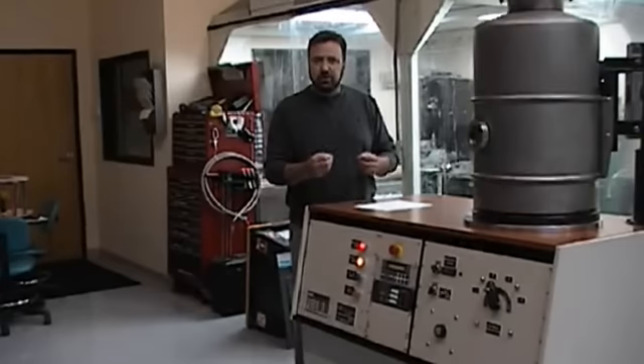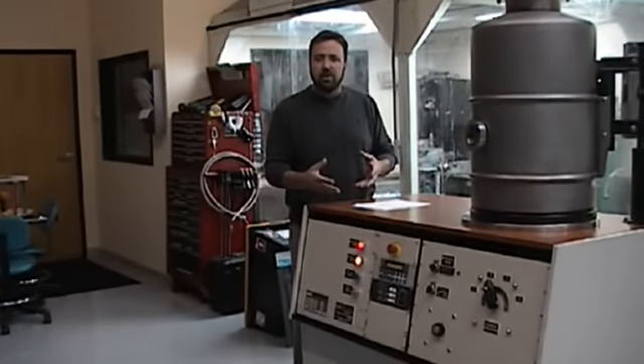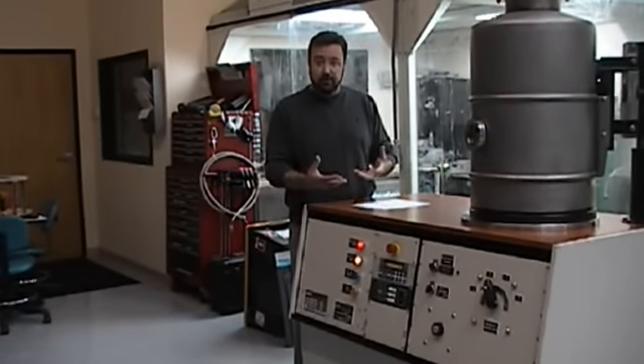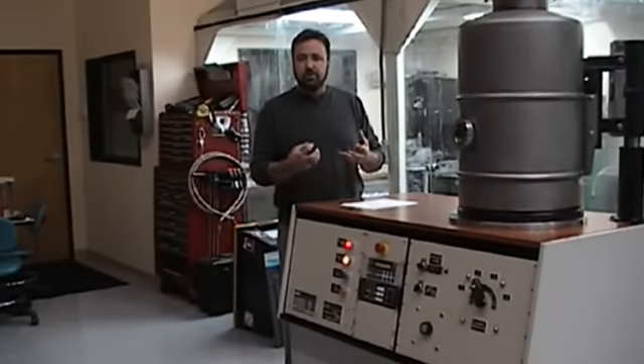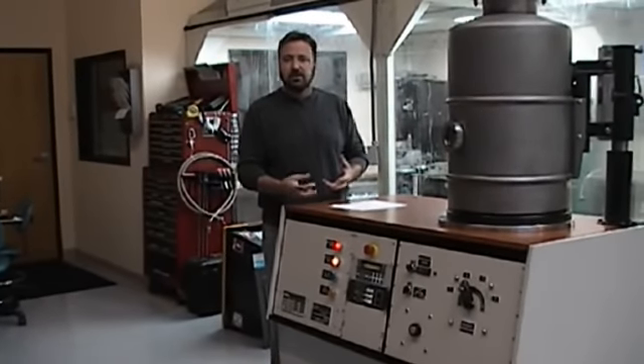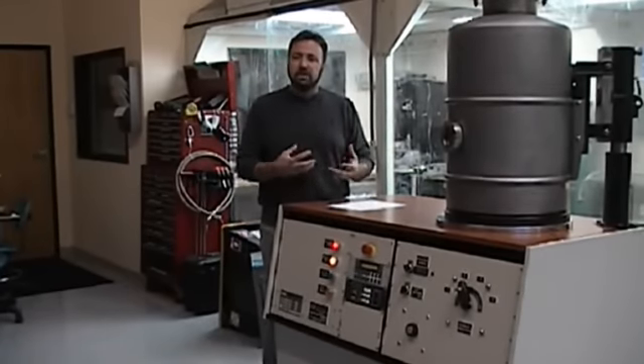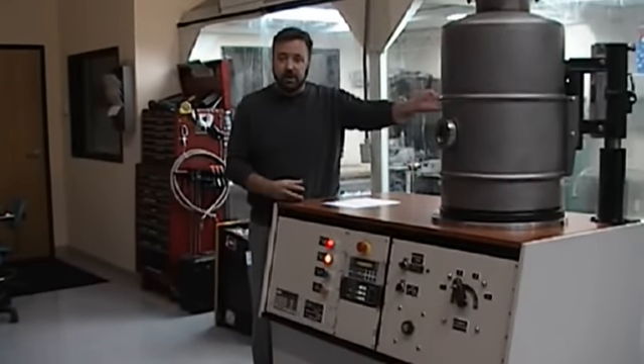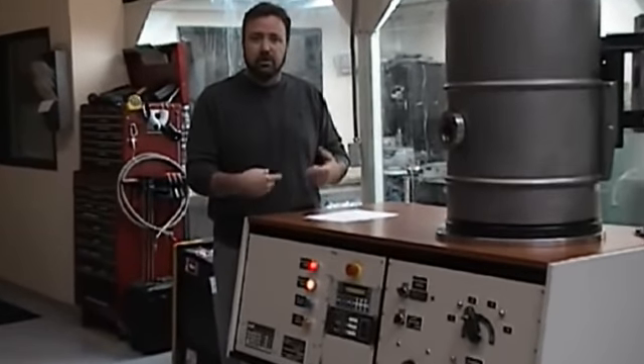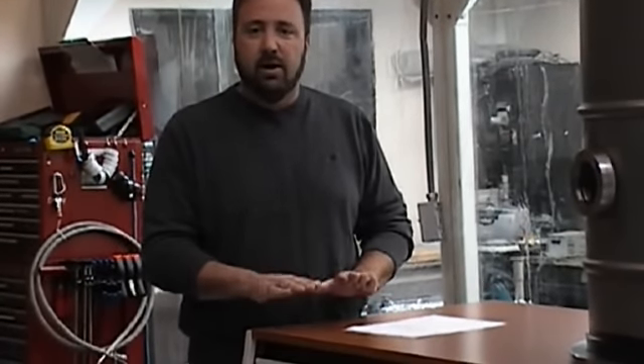The reason we do this is to dry the cryo pump. Inside the cryo pump, we have charcoal. The charcoal is used to absorb the non-condensable gases. What also happens is the charcoal absorbs the moisture inside the chamber. Every time you cycle the chamber, a little bit more moisture gets down.